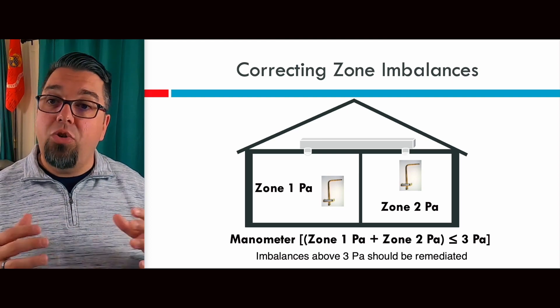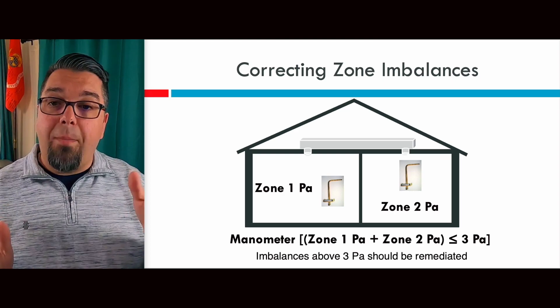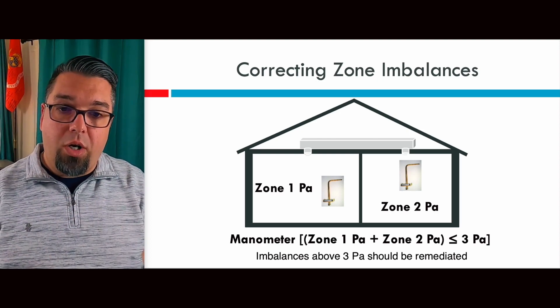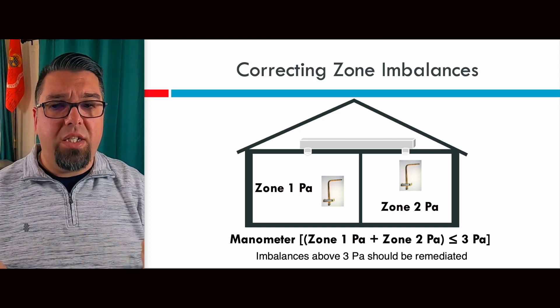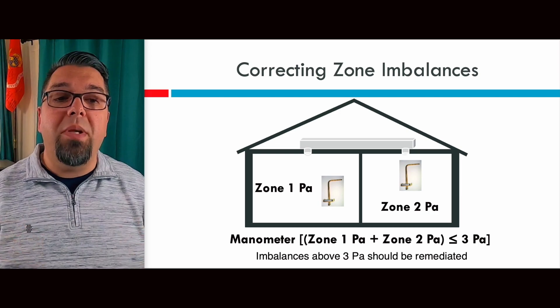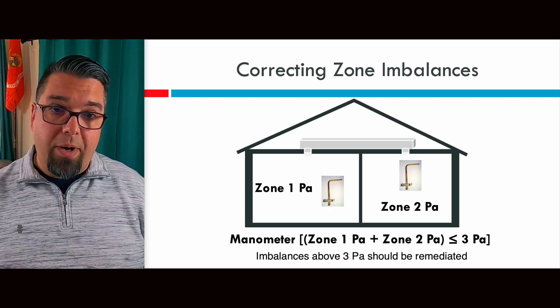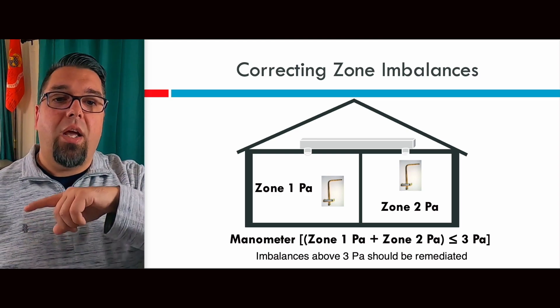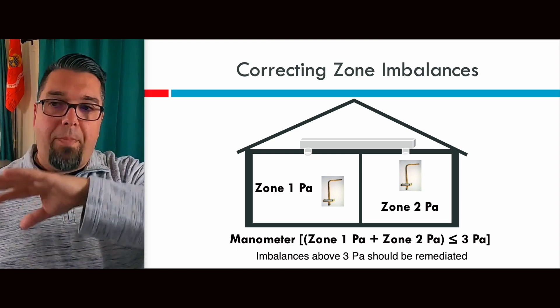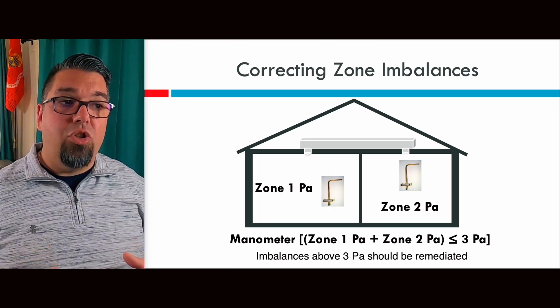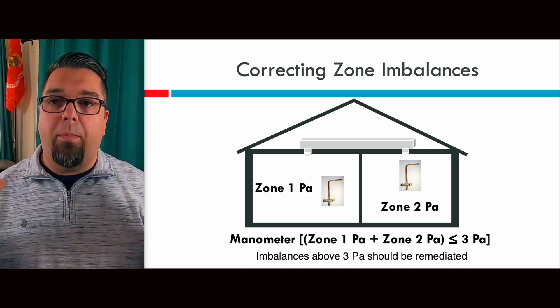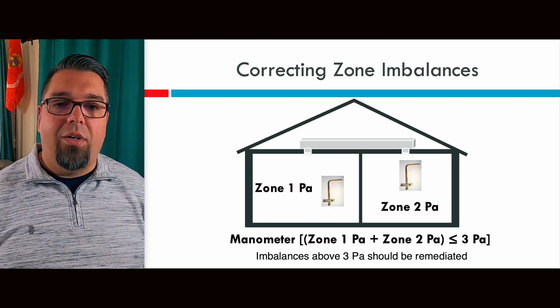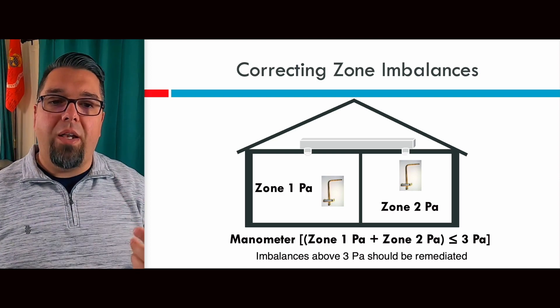When correcting zone imbalances, if you do this test and have more than a 3 Pascal difference — that's the pressure in metric — you need to remediate that space. Good dual-input manometers will measure Pascals as well as inches of water column. If you measure across zones and have more than a 3 Pascal difference, you need to remediate. That might be adding a return to a bedroom or putting in a jump duct across those bedrooms — but keep in mind, now you're going to be circulating air through an unconditioned space to balance it out. You don't want to depressurize a hallway and pull combustion product air back from the basement because now you've sealed everything up. 3 Pascals is the max — anything more than that, make sure you're remediating.